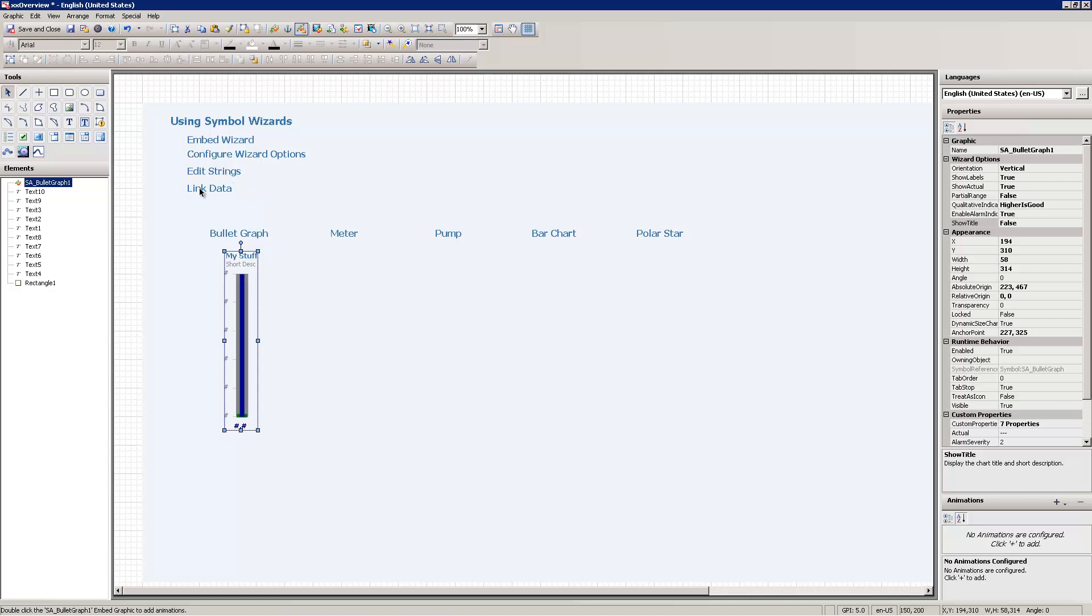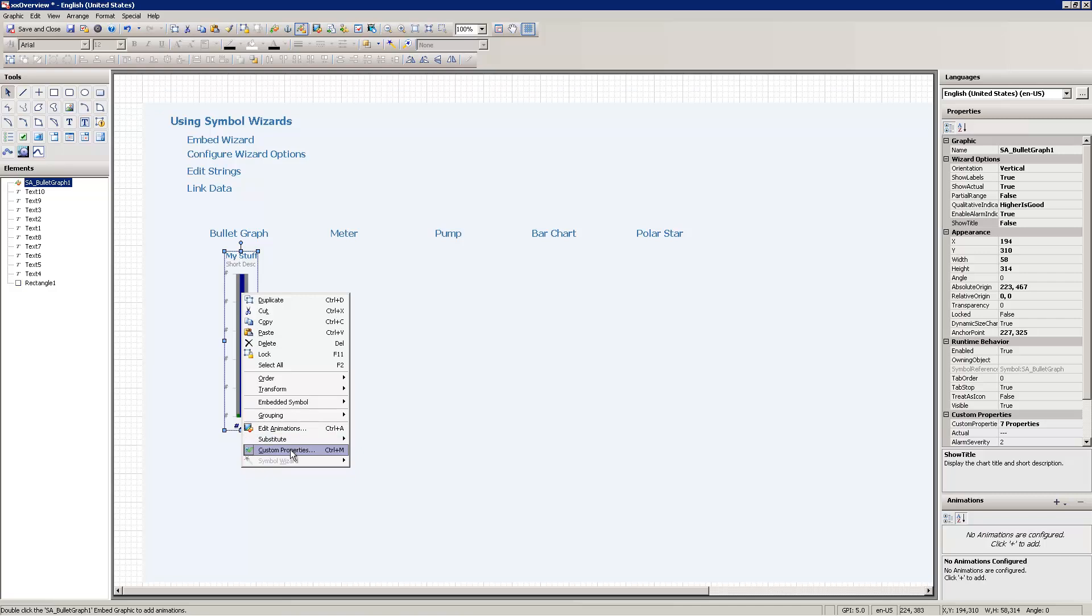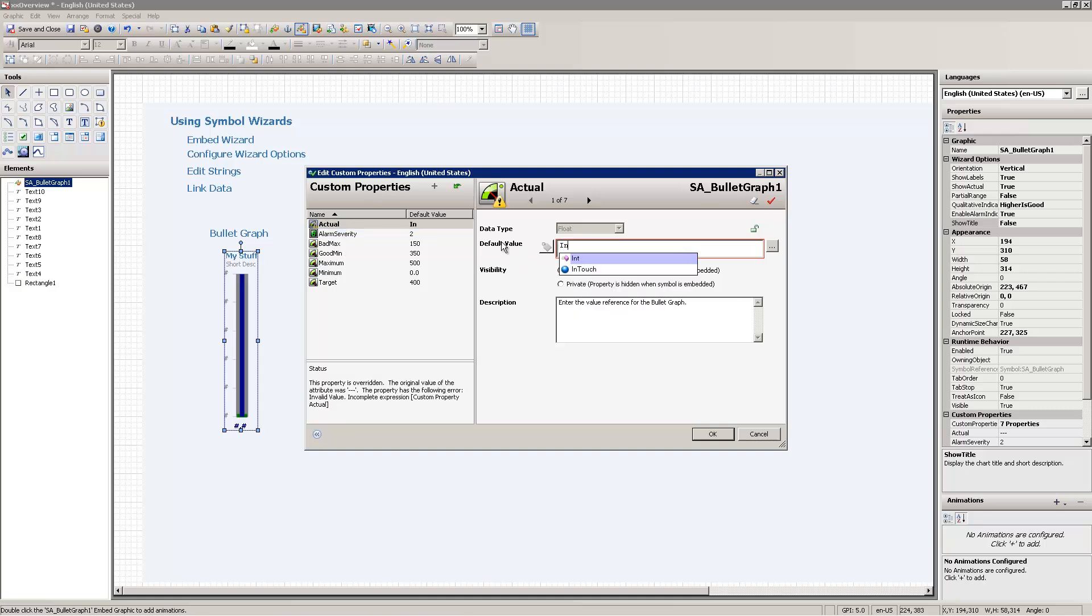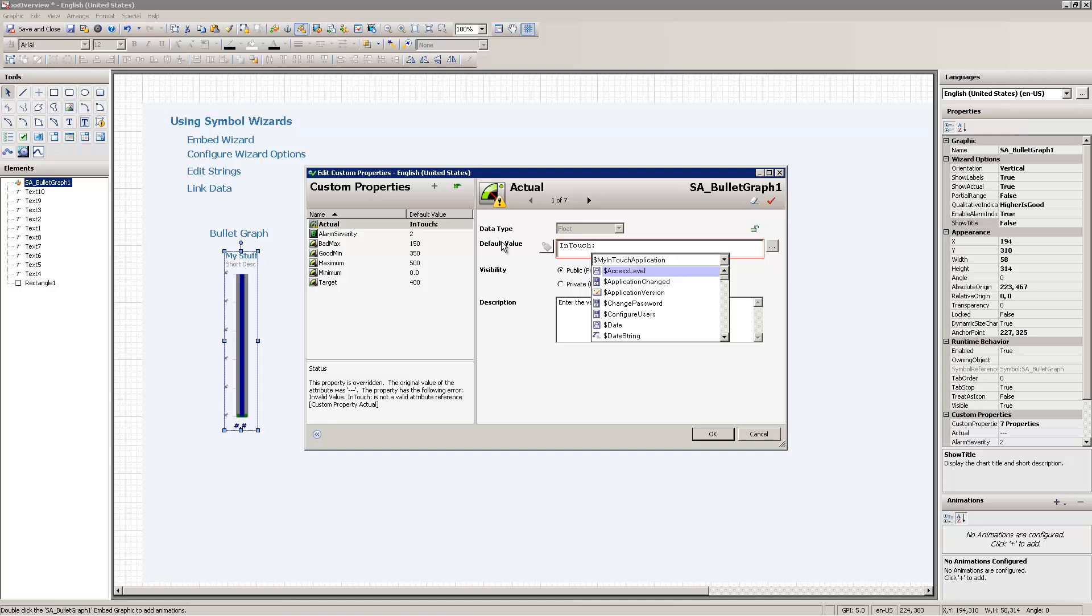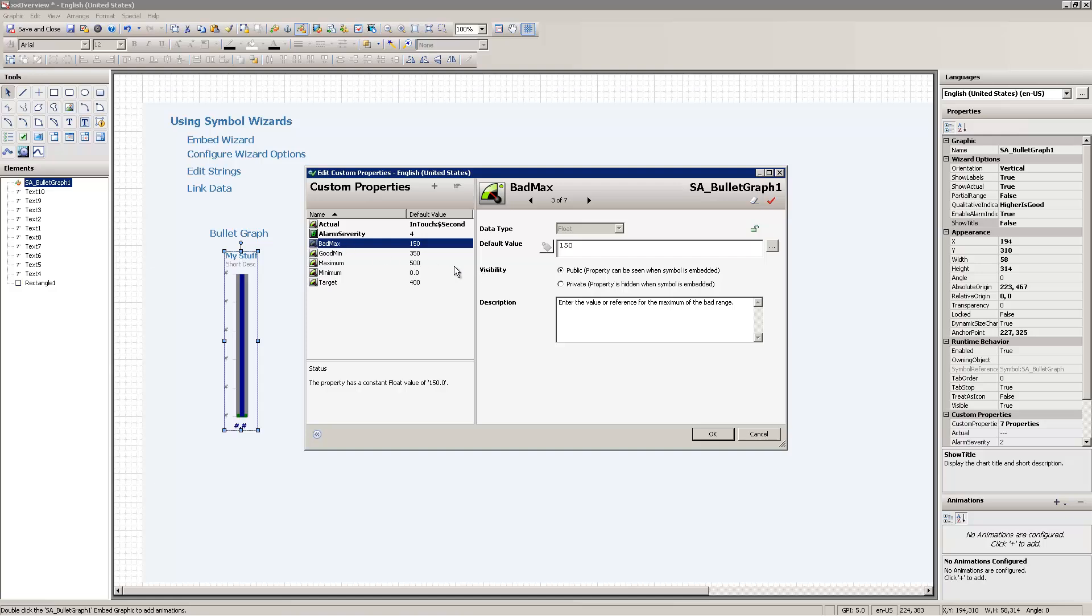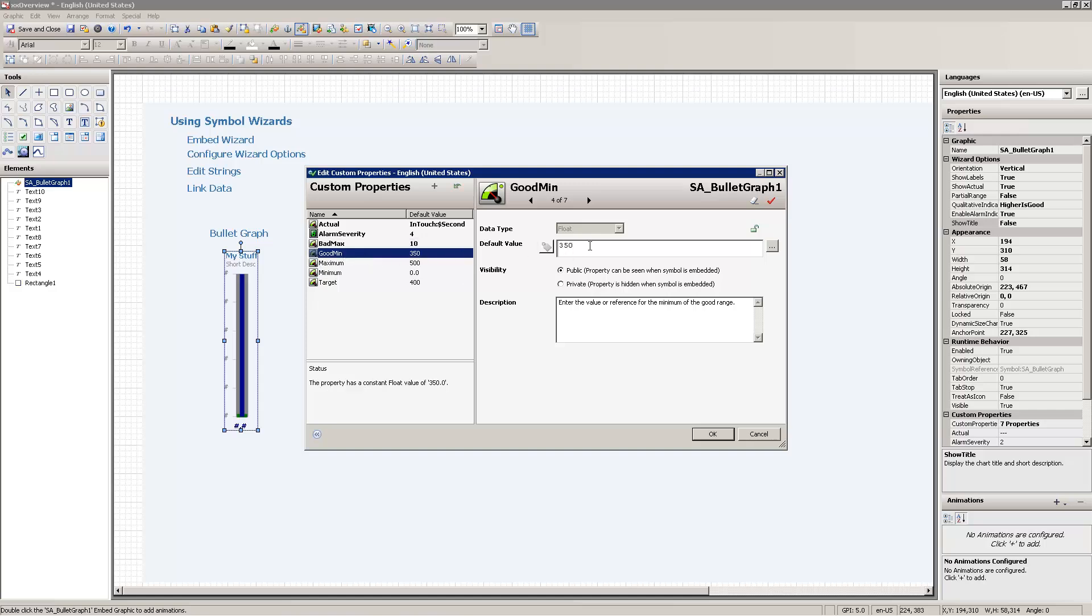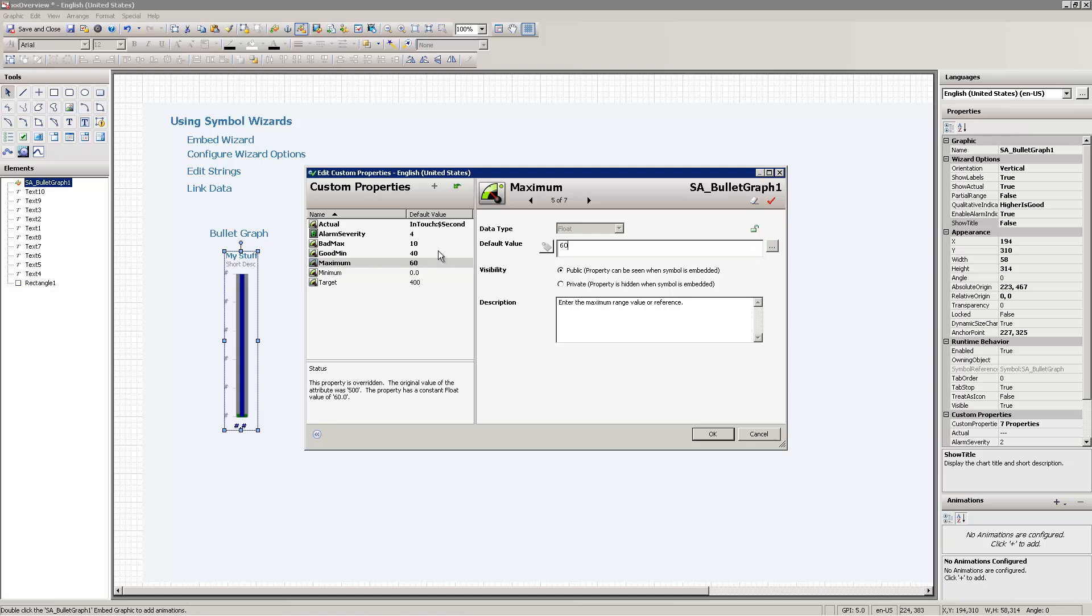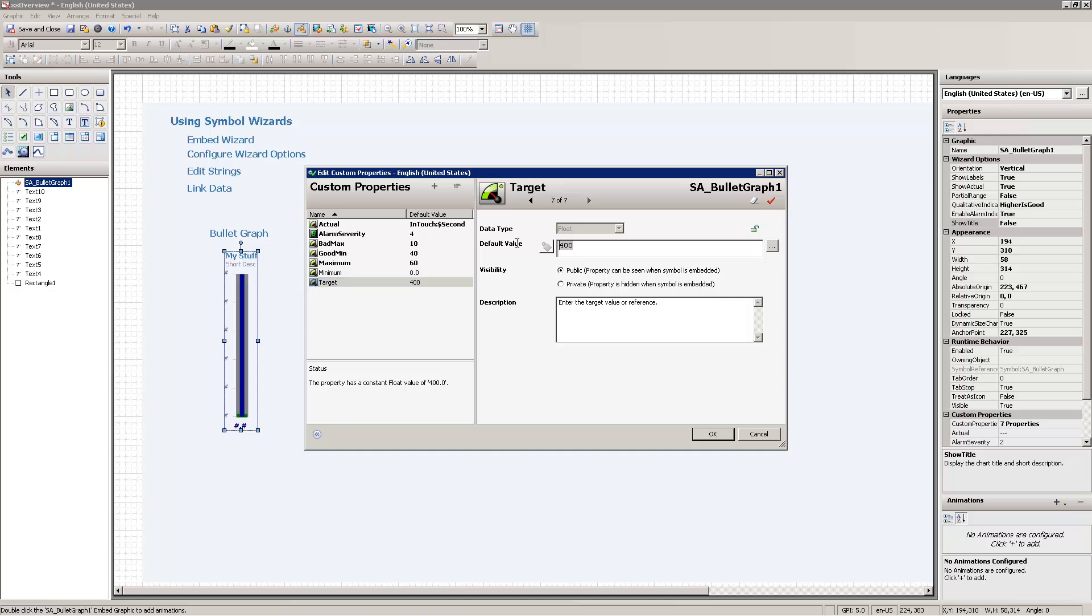I'm also now going to link the data. So I can link the data by accessing the custom properties, and here are all the properties that are exposed by this wizard. So here I'm going to use InTouch data in my example. So I'm going to pick InTouch colon dollar second to link that data in, and I'm going to change the rest of these variables up for something that shows a little bit better. So I'm going to change the alarm severity indicator to severity 4, change the bad max to 10, good min to 40, maximum 60. Target, I'll put that at 50.